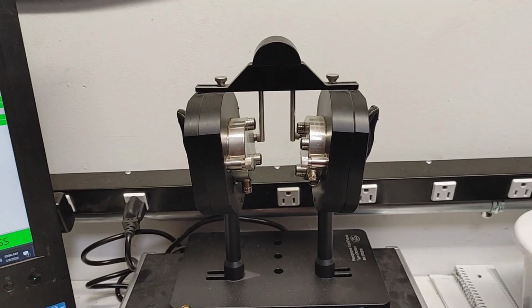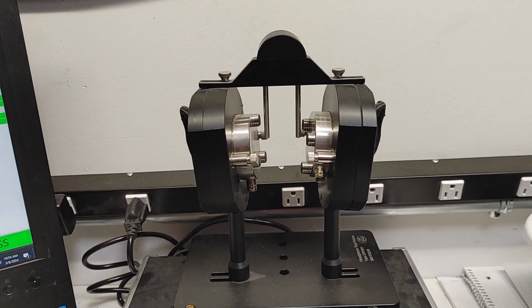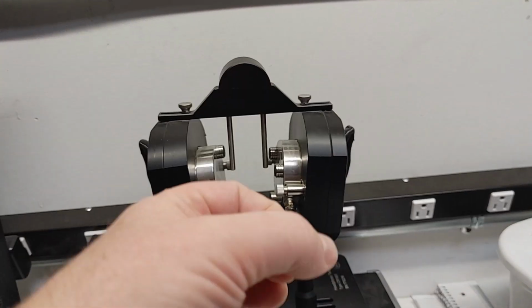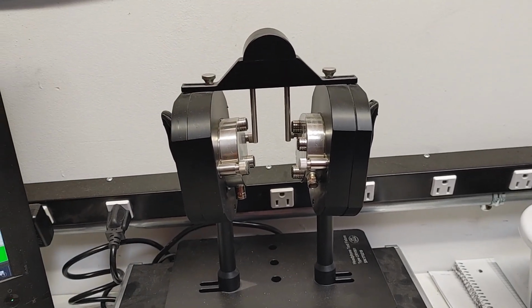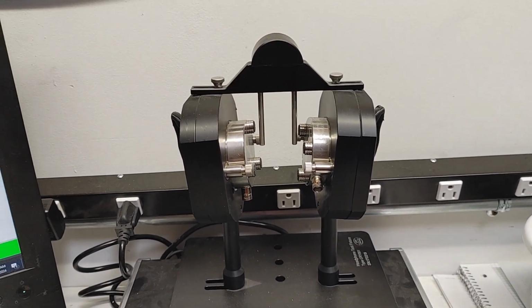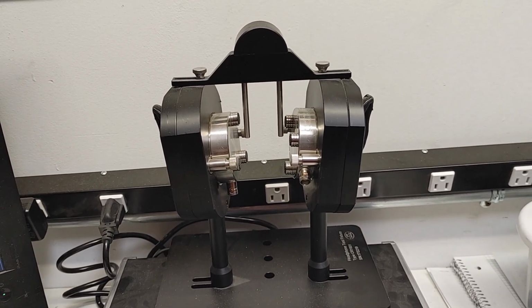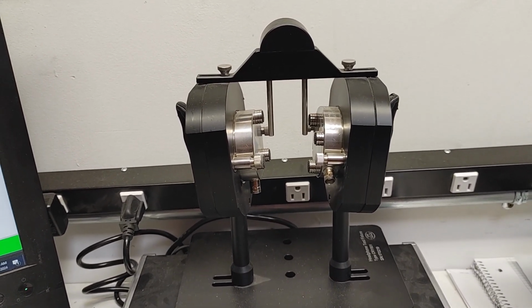A lot of you may have seen that a lot of places have what's called the Gras 45CA. It's basically a long horizontal tube. It's got slants on each side, a center post, and a little thing in the middle to hold the top of the headphone. You put it on, you measure it. Great. It measures really well. It's a great piece of gear. The problem is it's a fixed set of dimensions. It's for a nominal head dimension. And of course, as you know, none of our noggins are very much the same.